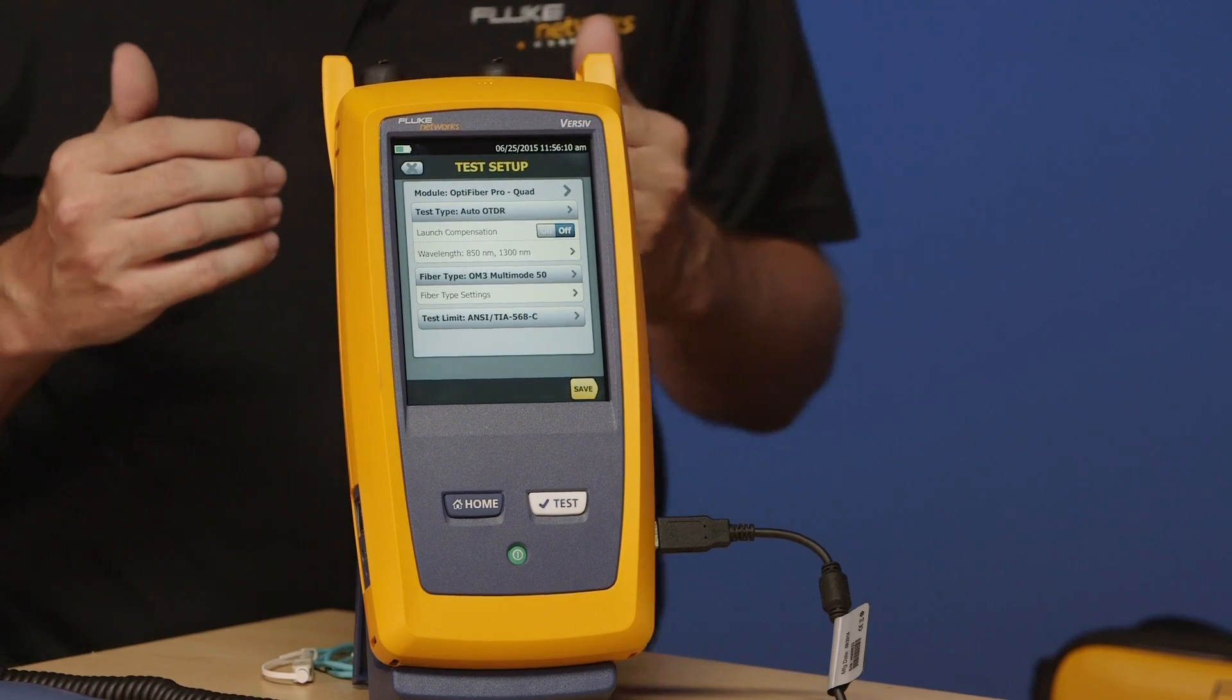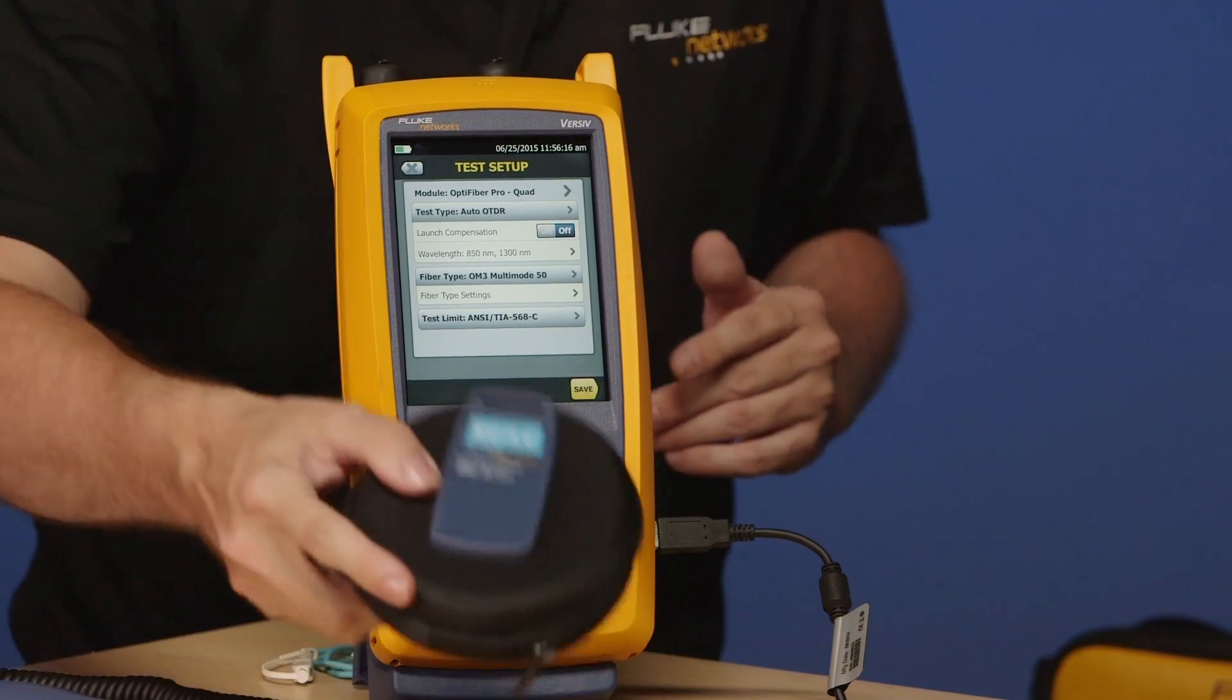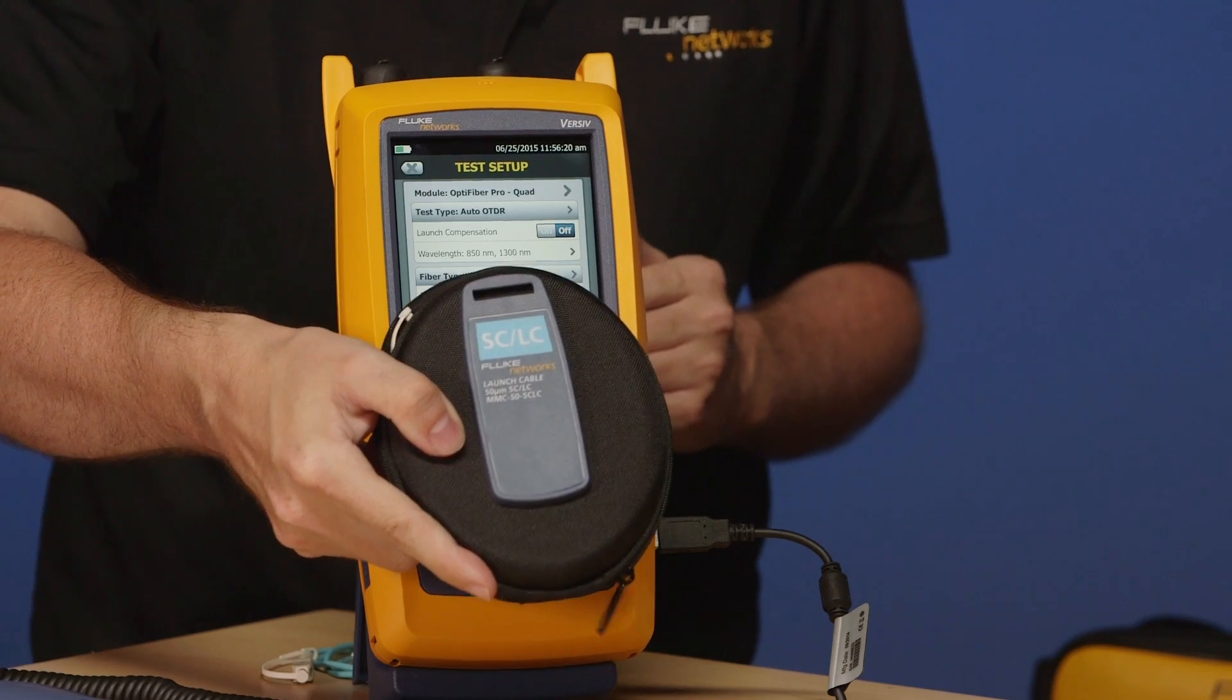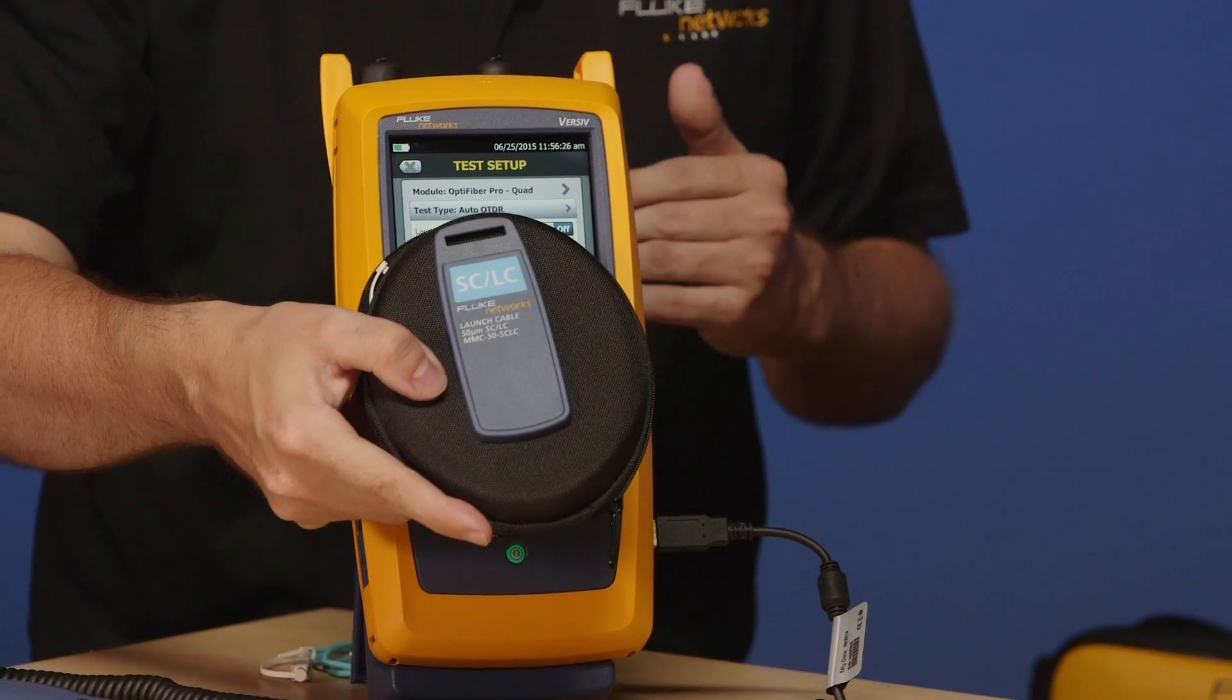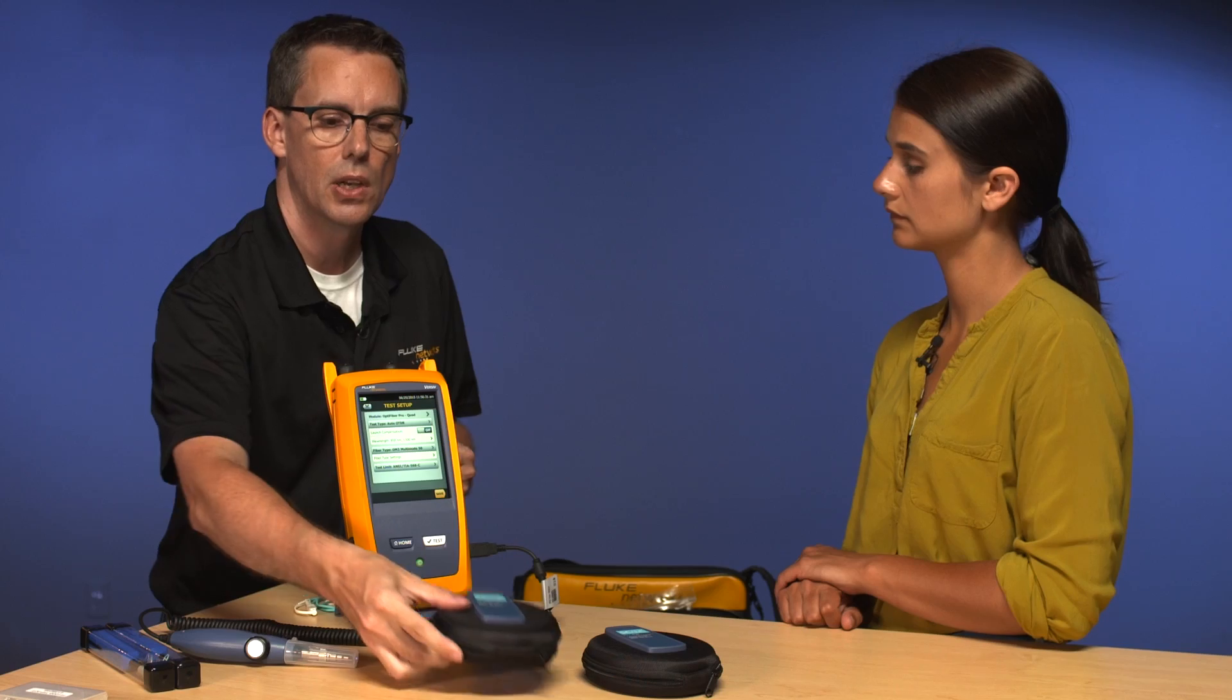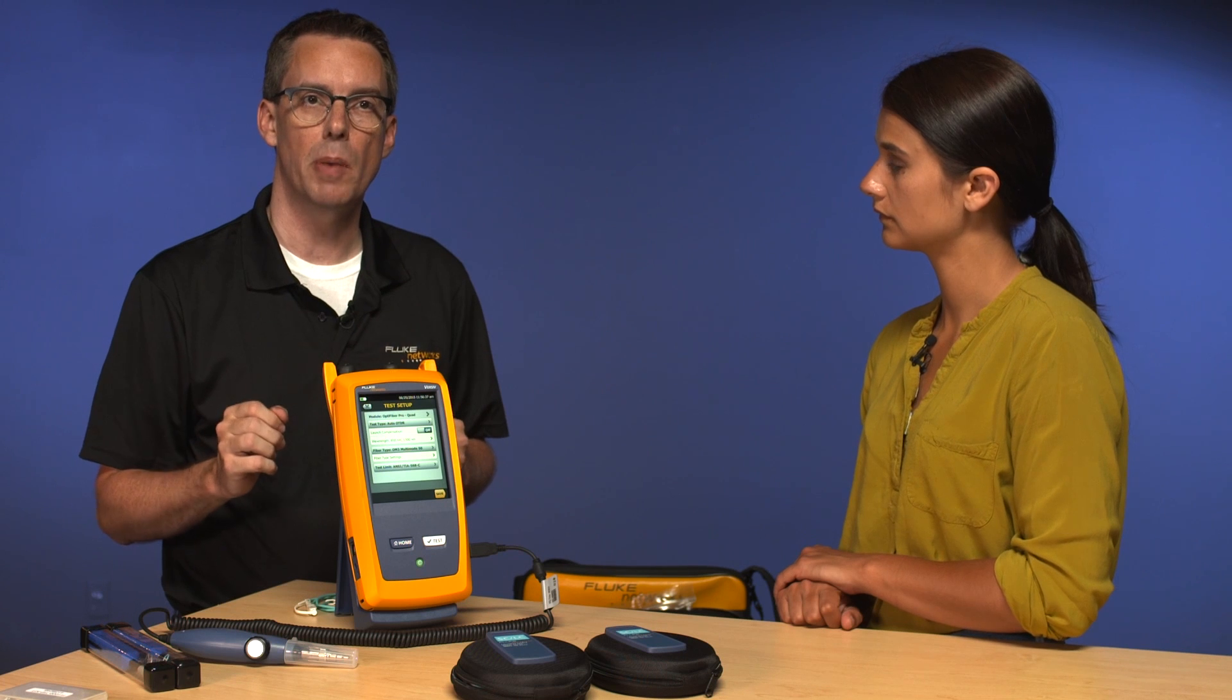And next thing down on my list here is the Launch Compensation. Now, whenever you do an OTDR measurement, you are going to be using a launch fiber. And it doesn't look like it. These launch packs contain about 105 meters of fiber. We have to connect that into the link, otherwise we're not going to see that first connection. Of course, we don't want this to be part of our measurement. So, what we'll do here in a moment is we'll actually remove that launch fiber from our measurement.